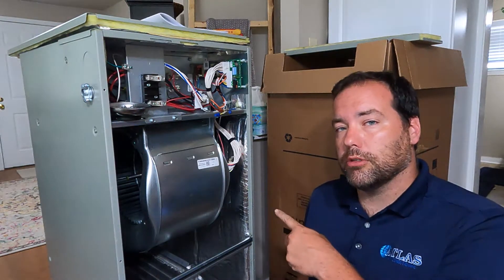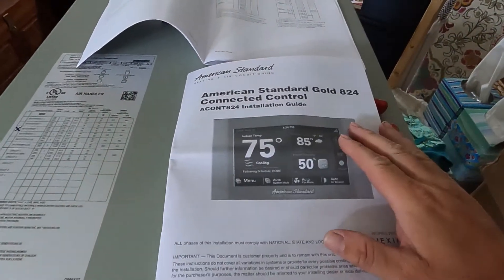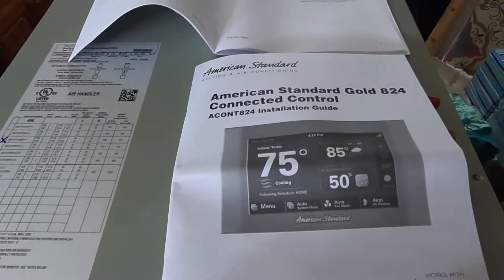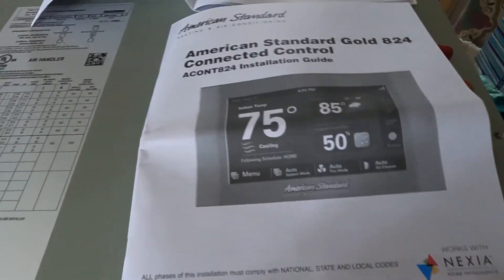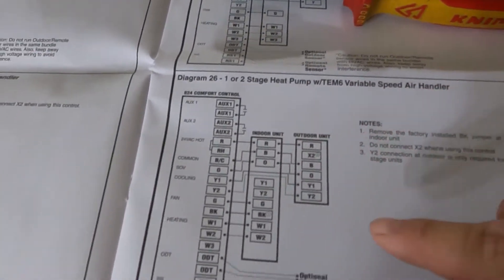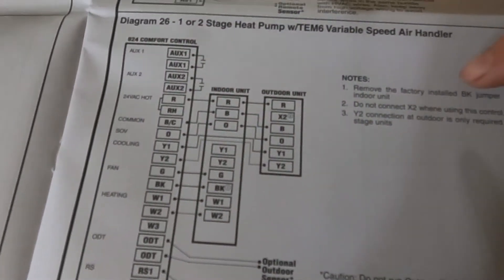The confusion usually starts because you get so many different wiring diagrams — they give you one for the air handler, one for the outdoor unit, one for the thermostat, and you don't know which one to use. If you're using a generic thermostat, use the one that comes with the air handler. If you're using a proprietary thermostat, use the manual that comes with that thermostat. You need to know what equipment you're working with. In this case I have a single-stage heat pump with the TEM6 variable speed air handler, so I'm using diagram 26. There are about 33 diagrams in this particular manual. I like to look at the notes first.